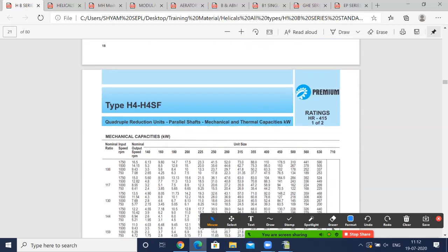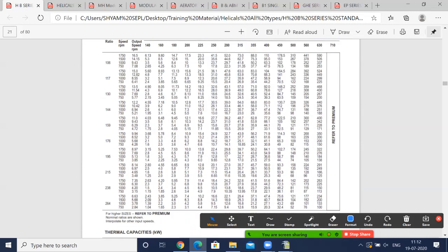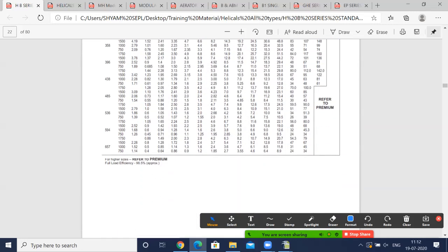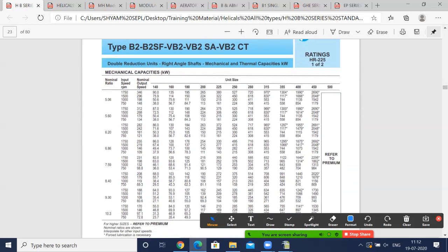In four stage, normally we don't give vertical, we give hollow output and standard. So the maximum ratio in that case is around 700. So you can go to a speed of less than 2 RPM if required. Okay. Then B2. Now what is B2?